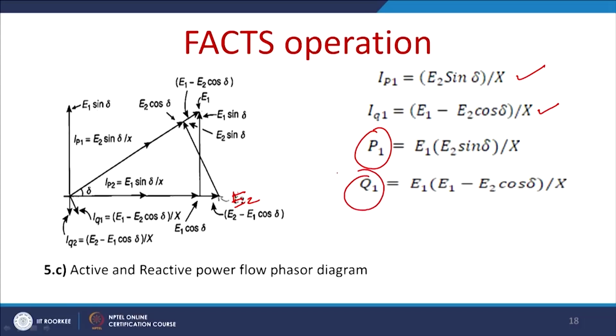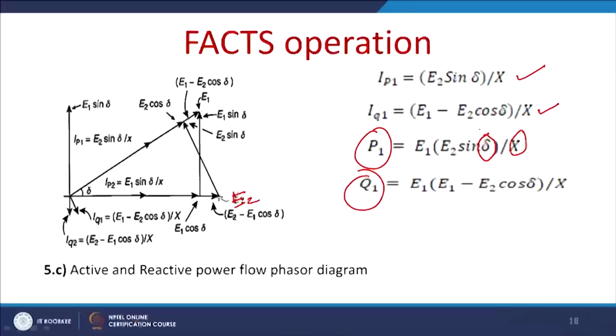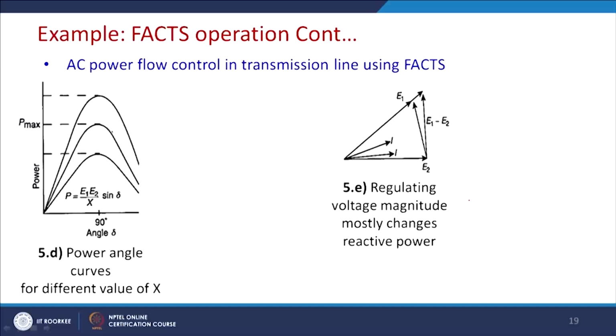Similarly, the reactive power from the sending end will be given by E1 into (E1 minus E2 cos delta) by X. Thus, as we understand, by changing X we can change the transmission capability of the line. Similarly, by changing delta we can change the transmission capability of the line. By increasing or decreasing the values of E1 and E2 we can also change the transmission capability of the line. In the same way, by controlling this term we can control the values of E1 and E2 in the line. So, if we wish to increase or decrease the power limit, we need to change the series impedance of the line. This will be the power curve.